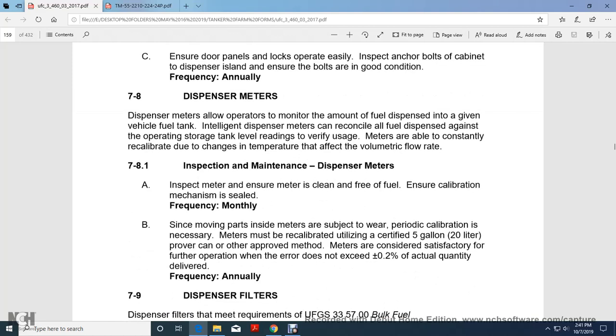Dispenser meters allow the operator to monitor the amount of fuel dispensed into the vehicle tank. Intelligent dispenser meters can reconcile fuel dispensed against the operating storage tank level, the tank ratings, and the verified usage. Meters are able to constantly recalibrate due to changes in temperature effect on the volumetric flow rate.